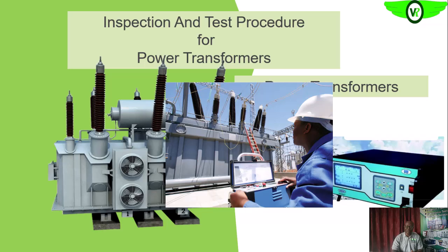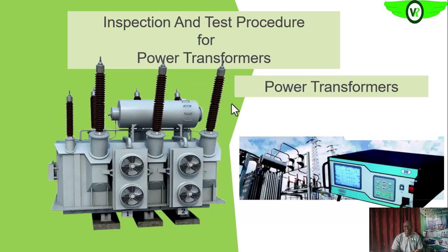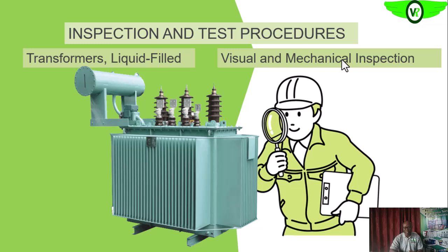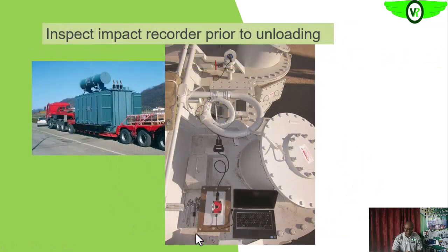All of these are meant to look at the physical and electrical integrity of the transformer. Under the visual or mechanical inspection, we look at the physical integrity of the equipment to ascertain that there are no dents and no external damages on the transformer. Look at the bushings for physical signs of cracks. Look at the fins for dents or signs of leakage. Look at the anchorage, especially for those that have been installed, to see that we do not have any loose ends. Okay, so we are going to look at this in a little more detail.